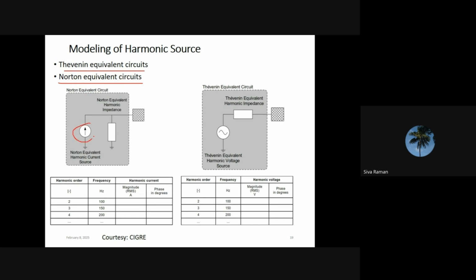So you see a current source with parallel impedance. The inverter manufacturers will provide this value. For example, this is the second order harmonic. For the second order harmonic, what is the current it will inject at this location? For example, it is 1 ampere. Then what is the impedance for the second order? Let's assume it is 0.3 ohm.